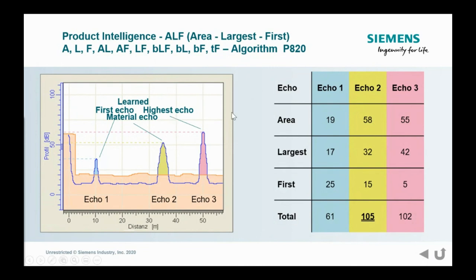Okay, you can actually adjust parameter P number 820, or in the new Hydroranger HMI, it's called algorithm, right? You can use just area, just largest, just first, area and largest, area first, largest first, and then you can use best of largest and first, best of largest, best of first, or true first, okay? And so you can adjust that parameter to try and pick the one. In this case, maybe we might choose largest, right? Because largest is my true echo, and then it would basically, the one that has the highest score in largest, in this case that would be echo number three, would be the one that it selects.